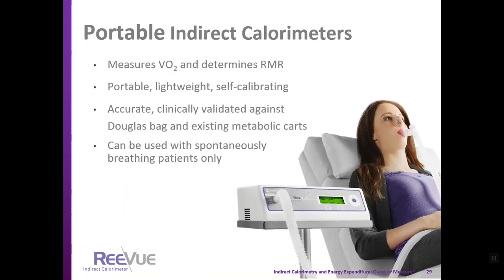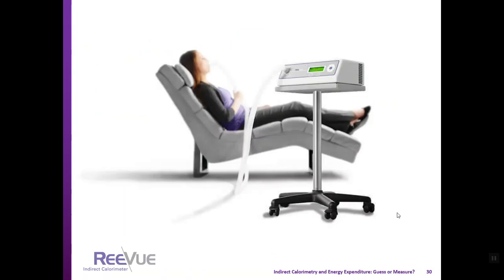There are portable indirect calorimeters that measure oxygen consumption to determine resting metabolic rate. One example is the MedGem/Reevue device, which is portable, lightweight, and self-calibrating. It has been clinically validated against Douglas Bag and existing metabolic carts, and is used with spontaneously breathing patients only. Patients use nose clips and a mouthpiece during measurement, and are typically in a supine position.